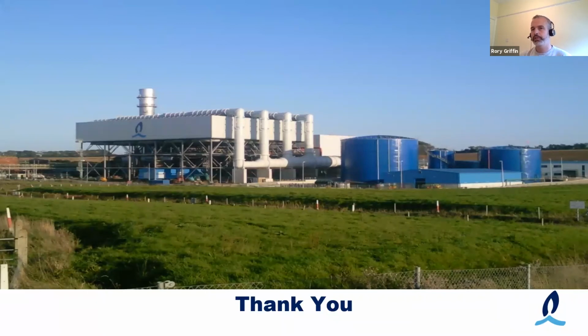If the nature of the blackout was that the station ended up blacked out as well, so let's say the breaker didn't open on the connection point, but just the voltage collapsed in the southern region, then there's a couple of things that will depend how quickly something like Whitegate can come back. So you'd have to check the integrity of the plant, but also then you're looking at areas like the boiler. Have you retained drum levels?